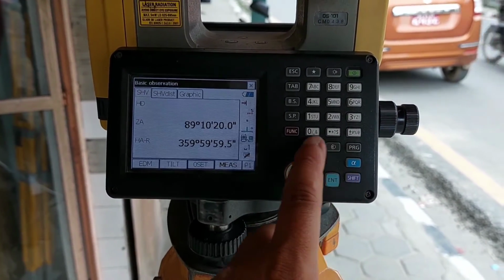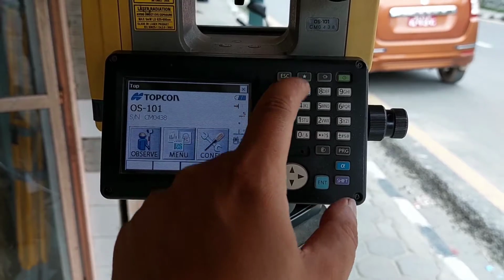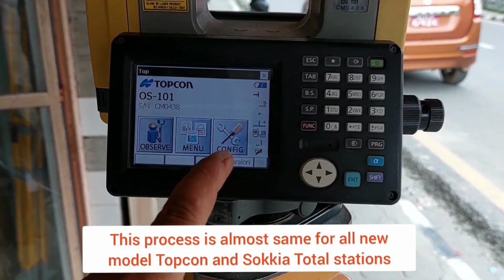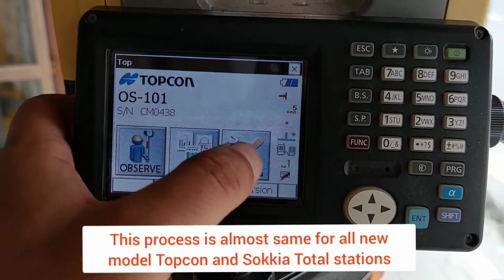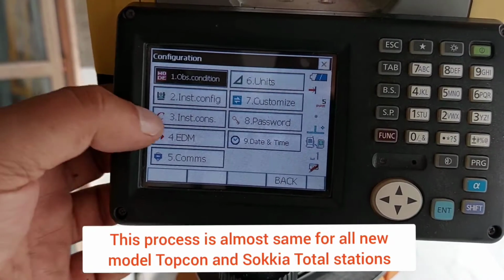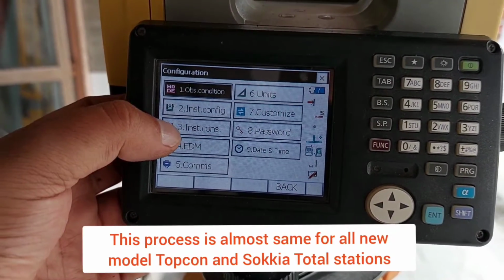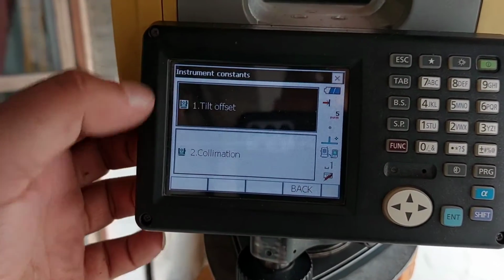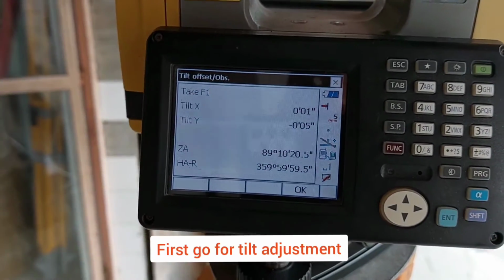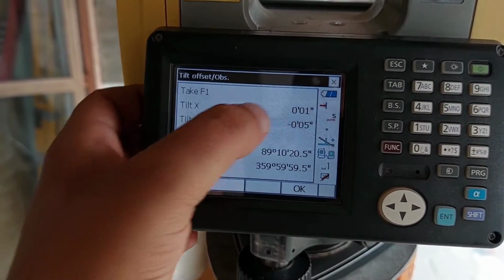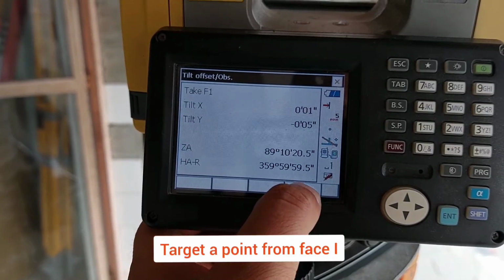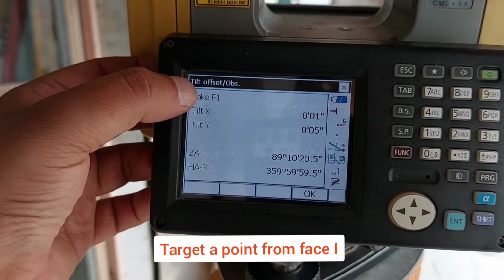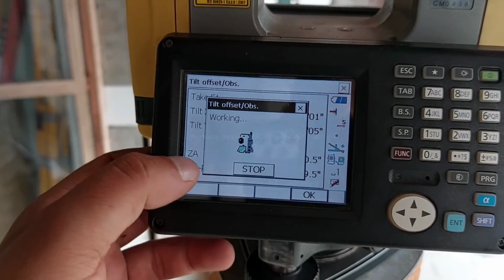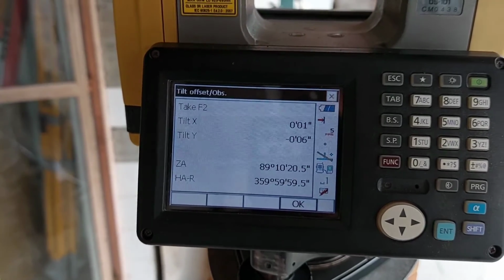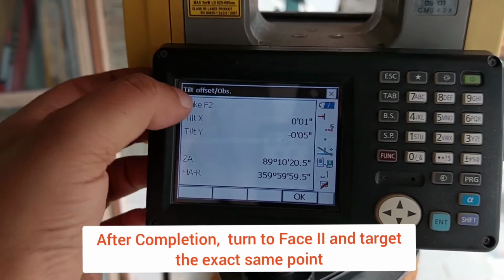So for calibration, now we need to go to escape and go to configuration. You can see it configuration. Okay, now click there and inside configuration there is instrument constant. Okay, under instrument constant there is tilt offset and collimation. First go to tilt offset calculation. There you can see it. Okay, take F1 and tilt of X and Y is shown. Okay, now press OK. Now it will ask you to take F2.